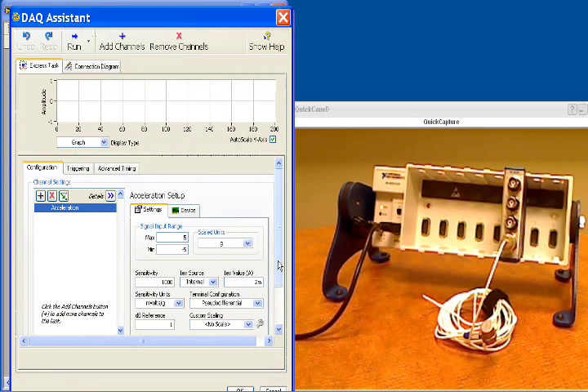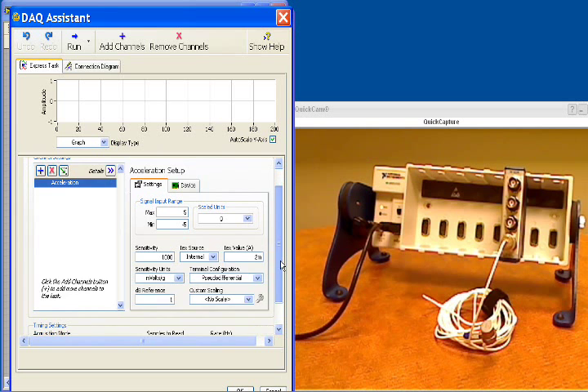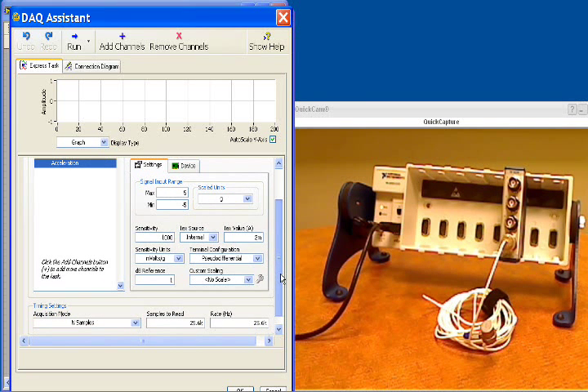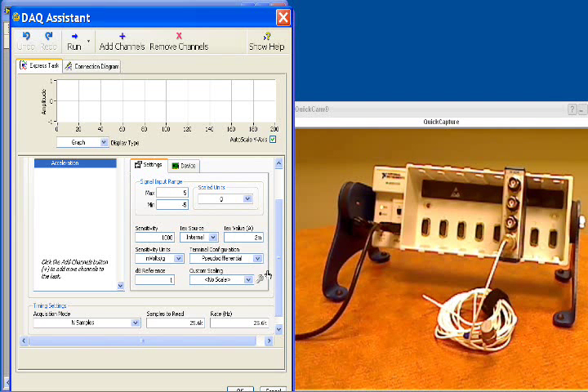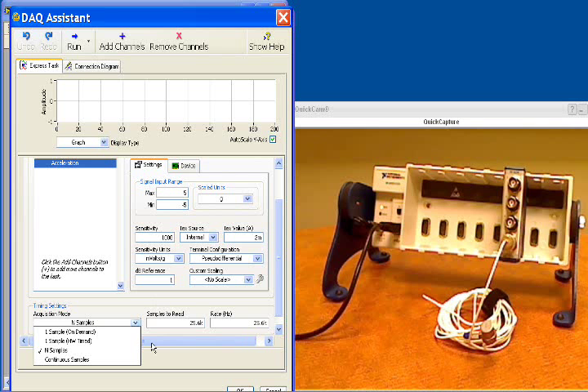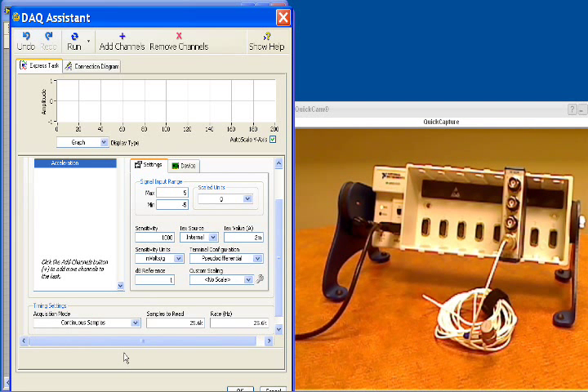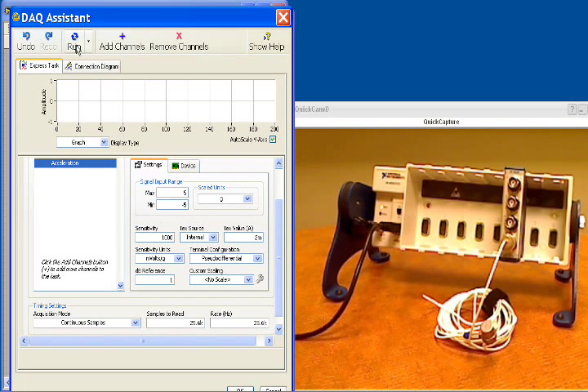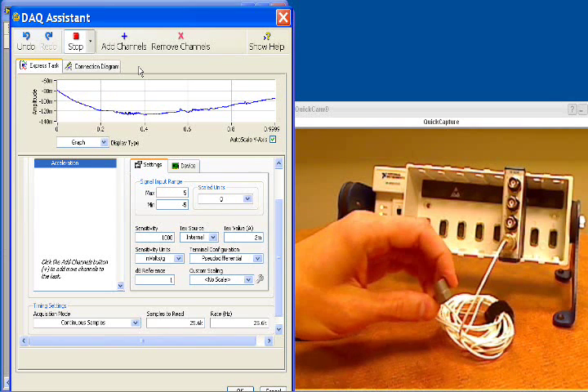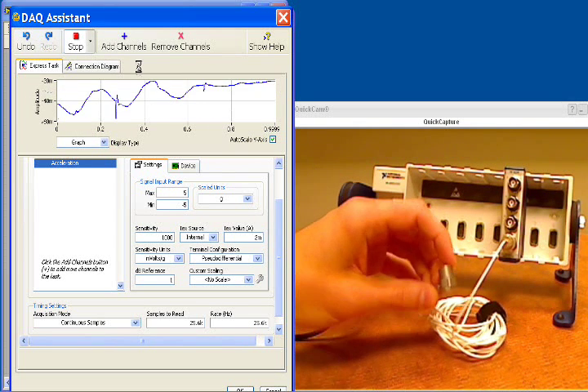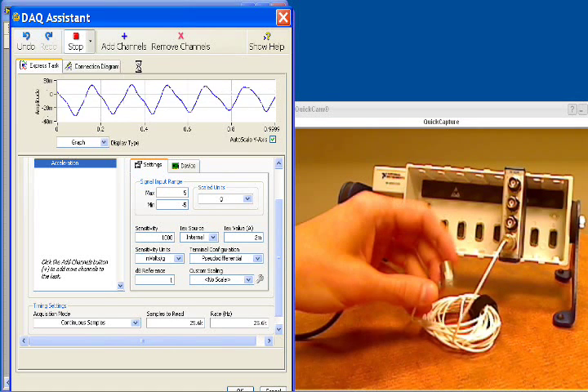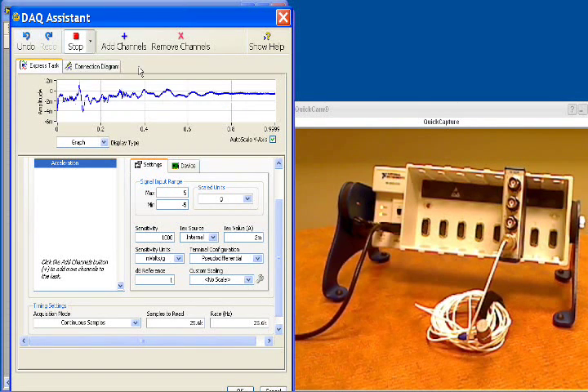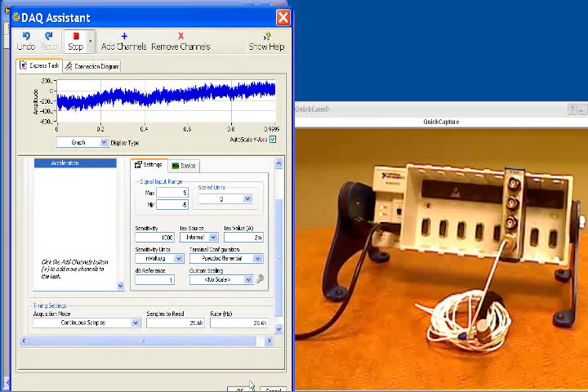And now I can open up my accelerometer data sheet and see the sensitivity. And 1,000 is about correct for this accelerometer. For the acquisition timing, I want to do a continuous acquisition because we're going to monitor frequency over time rather than just a snapshot. And really that's going to configure it for this accelerometer. So I'm going to click run real quick and pick up my sensor. And you can see if I shake it, I can see that my accelerometer seems to be connected correctly. And I'm going to say that looks good and click OK.